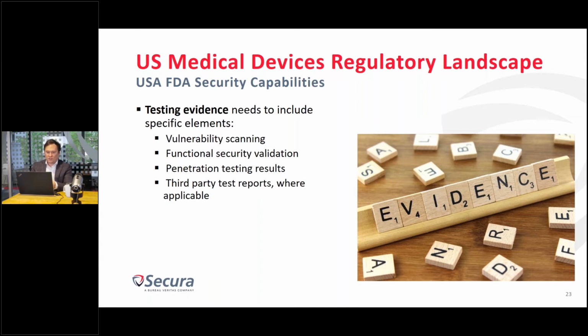But also one level further: penetration testing, which assumes the security functionalities are already in place but tests their robustness and efficiency against potential attacks. Vulnerability scanning evidence needs to be provided by the manufacturer, and also, where applicable, third-party test reports for particular security features or components that cannot be tested by the manufacturer itself due to lack of capacity, time, or security expertise.